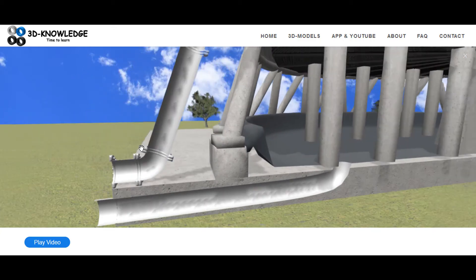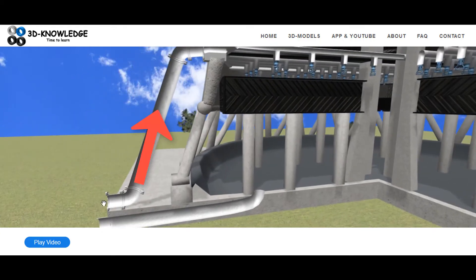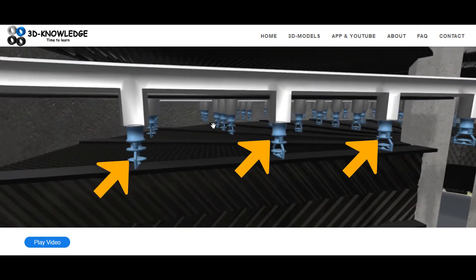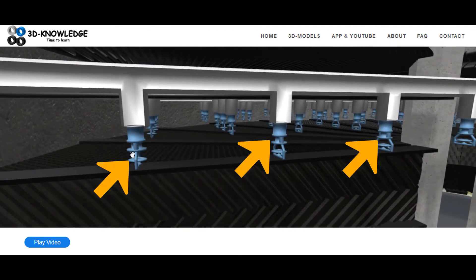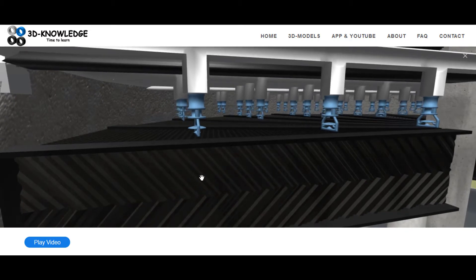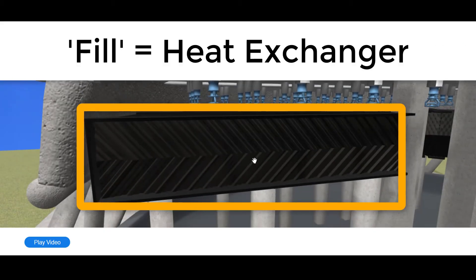It comes back at a slightly elevated temperature through this pipe here and is discharged through spray nozzles. The spray nozzles then spray onto fill, which is a large heat exchanger where the water is brought into contact with air over a large cross-sectional area.